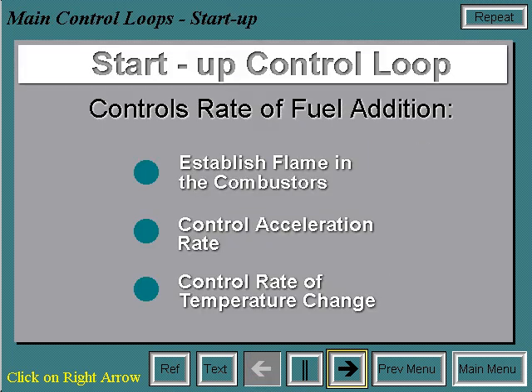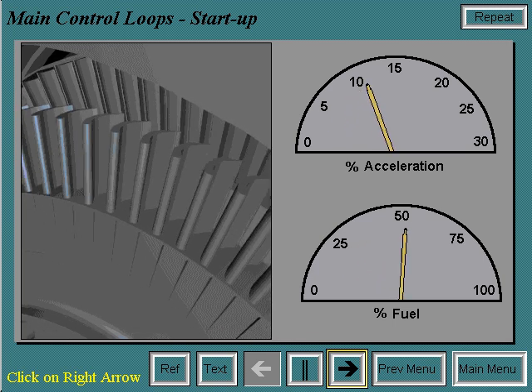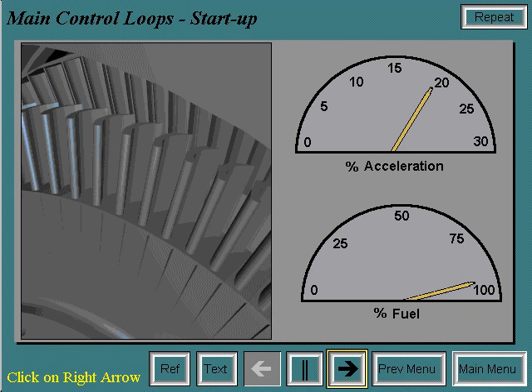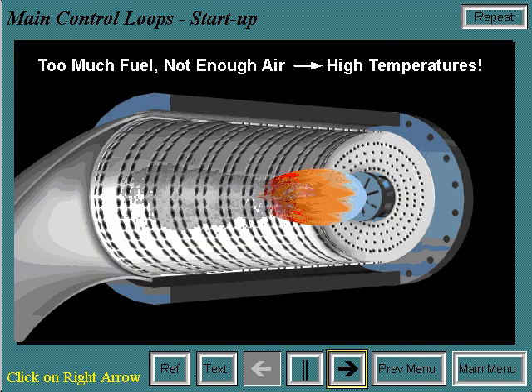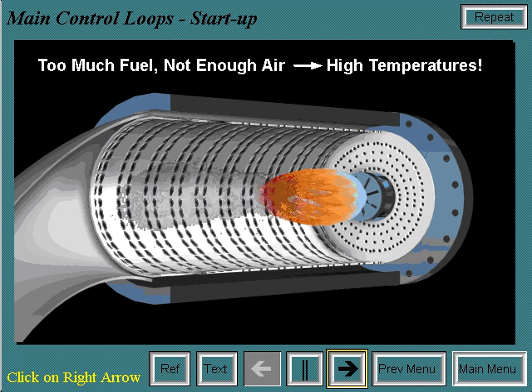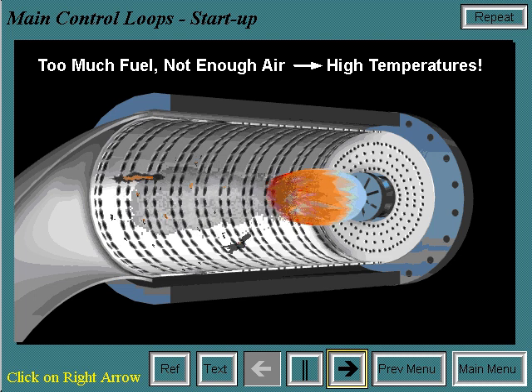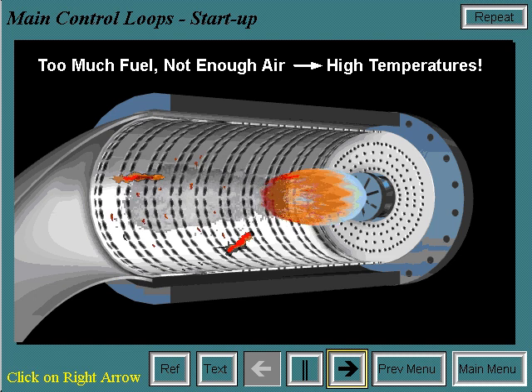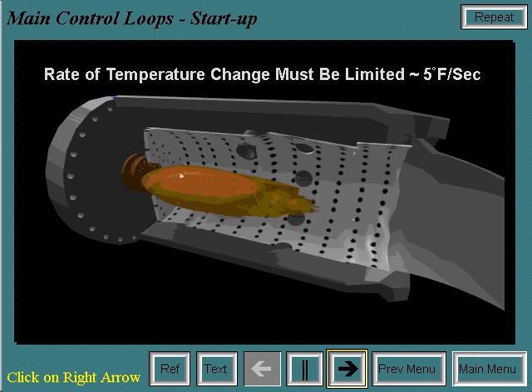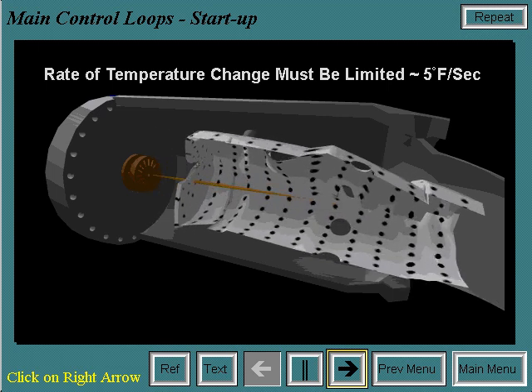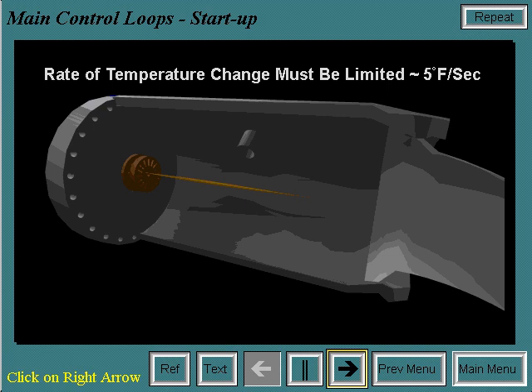The start-up control loop controls the rate of fuel addition for several reasons: to establish flame in the combustors, to control the acceleration rate, and to control the rate of temperature change. Acceleration of the turbine rotor must be controlled so as not to exceed the allowable forces on the rotor, as exceeding the limit can cause heavy damage. During start-up, airflow rates are low. If there is too much fuel added while there isn't enough air, temperatures could get dangerously high, potentially damaging internal hardware. High fluctuations in temperature can reduce the life of the internal hardware, and the rate of temperature change must be limited at approximately 5 degrees per second since different materials heat at different rates.